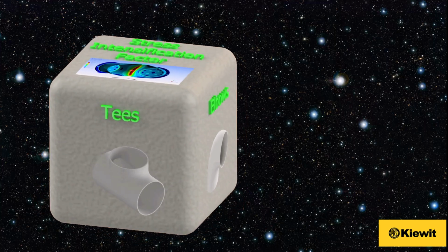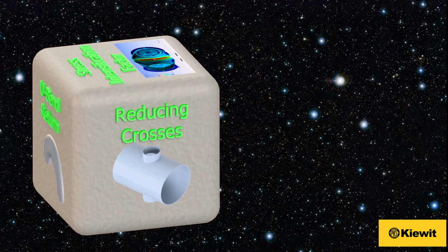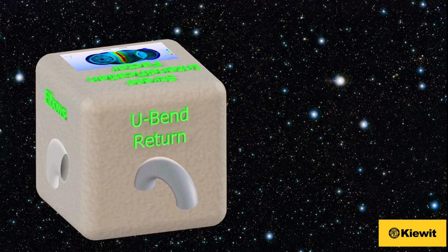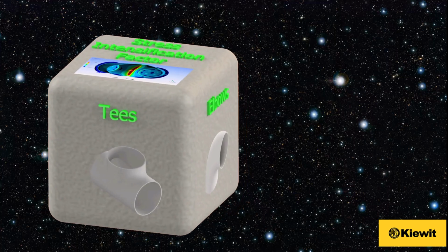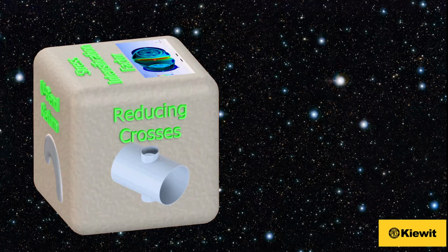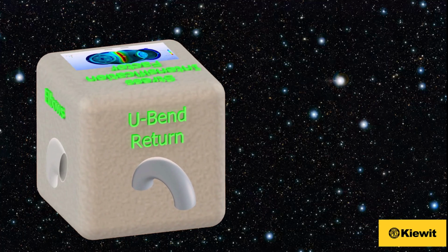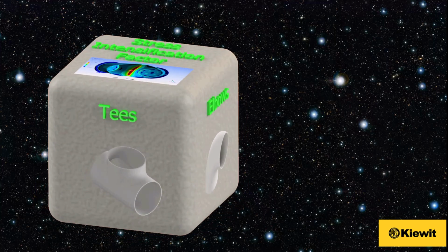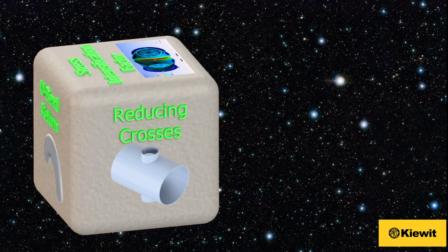Well, it is simply a factor that is added per component to the pipe stress calculation for that wall thickness that accounts for the geometry of that component and the related stresses because of that geometry for stress calculation. Simply stated, it is the pipe stress calculation for straight pipe as if there were no component there times the associated stress intensification factor for that component geometry to account for the presence of that component.